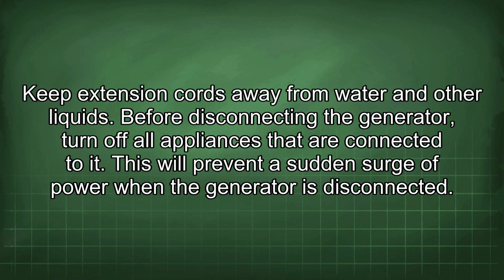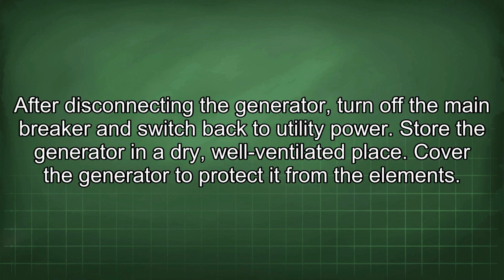Before disconnecting the generator, turn off all appliances that are connected to it. This will prevent a sudden surge of power when the generator is disconnected. After disconnecting the generator, turn off the main breaker and switch back to utility power. Store the generator in a dry, well-ventilated place. Cover the generator to protect it from the elements.